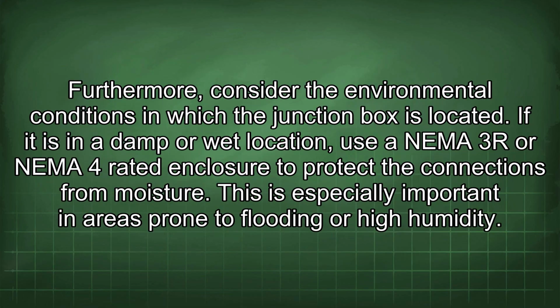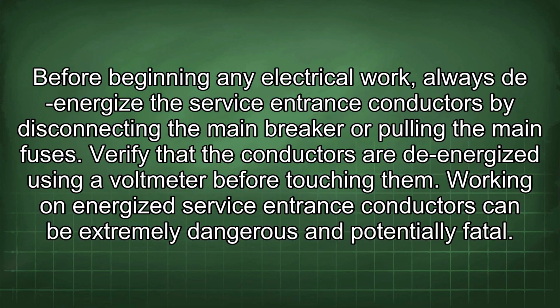Furthermore, consider the environmental conditions in which the junction box is located. If it is in a damp or wet location, use a NEMA 3R or NEMA 4 rated enclosure to protect the connections from moisture. This is especially important in areas prone to flooding or high humidity. Before beginning any electrical work, always de-energize the service entrance conductors by disconnecting the main breaker or pulling the main fuses. Verify that the conductors are de-energized using a voltmeter before touching them. Working on energized service entrance conductors can be extremely dangerous and potentially fatal.